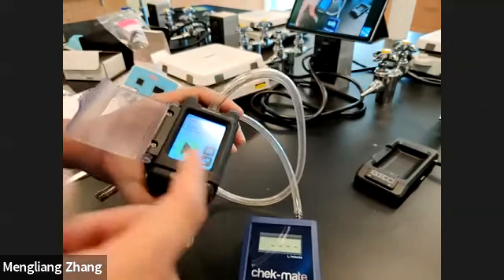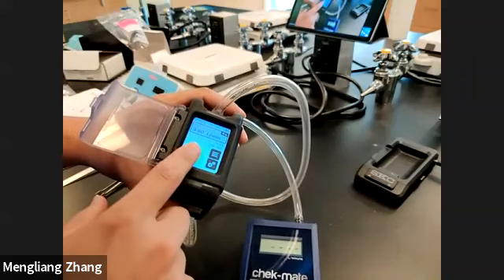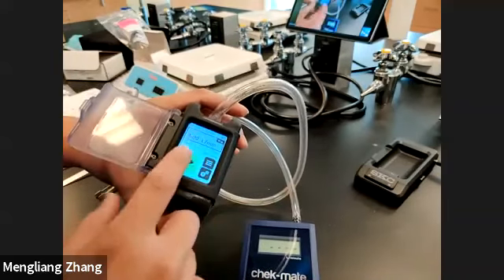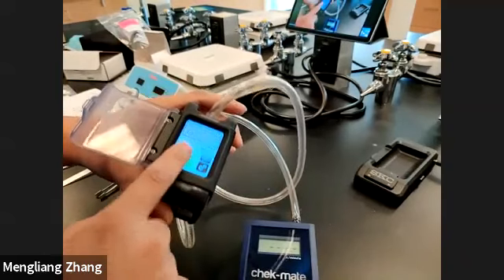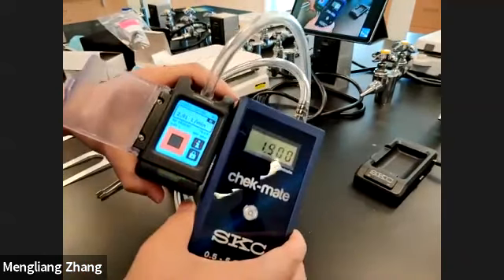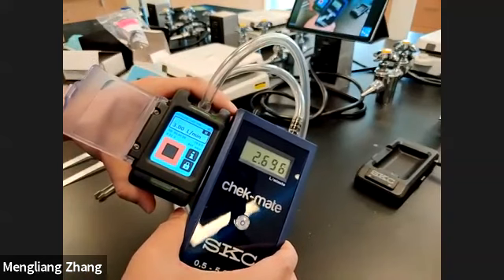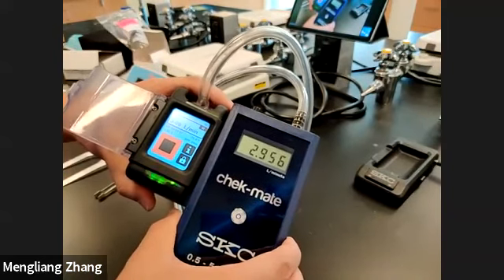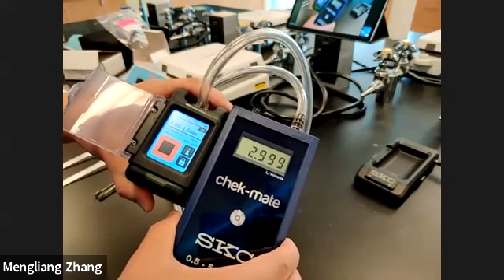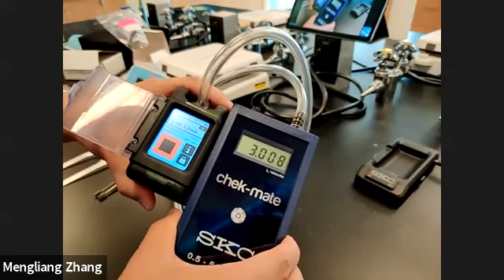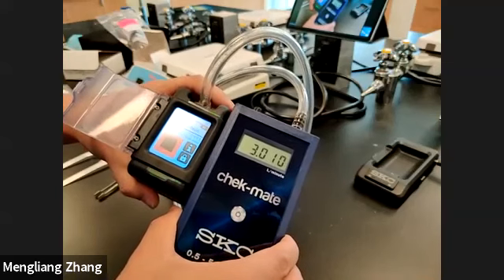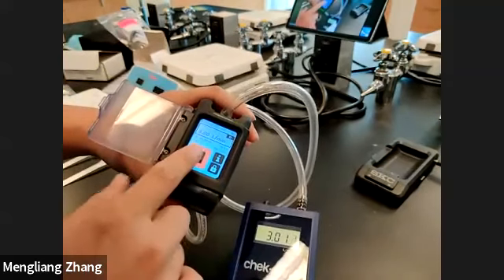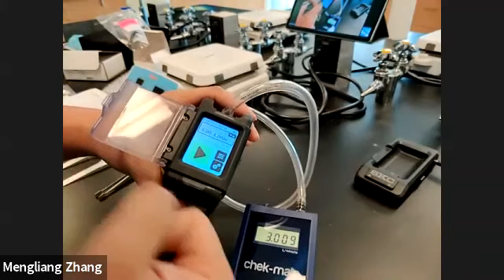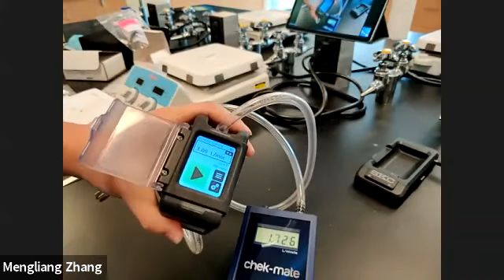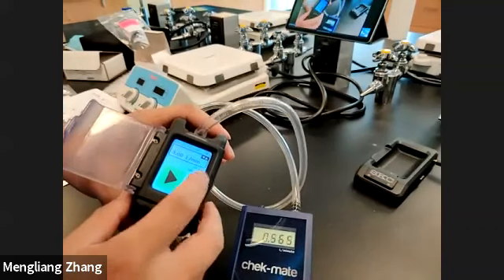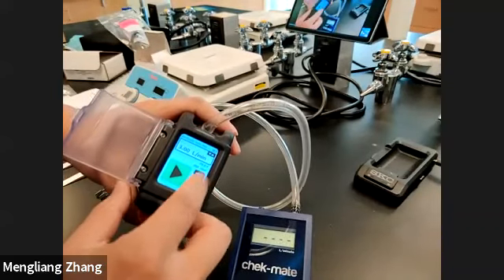Once you calibrate this pump, all you need to do is click the run button to test again. In this case, I press the run button and double check the airflow from the pump. Okay, it's very close to 3.0. It's 2.999 or 3.008. So that should be good enough for the experiment or sample collection. And here I want to stop the pump, because for the real sample collection we can set up a program. In this case, we can select the program button, which is second to the bottom.